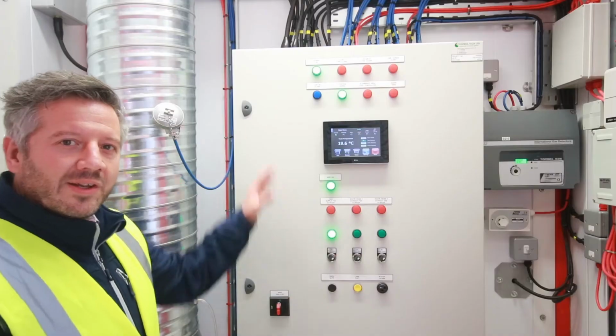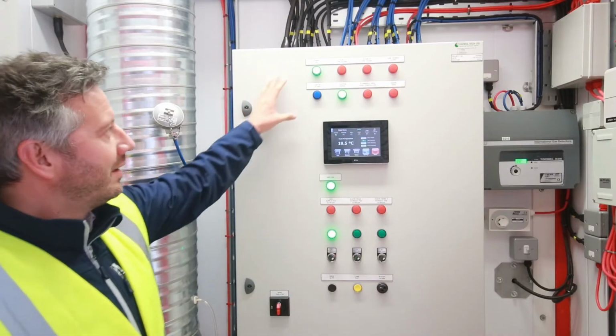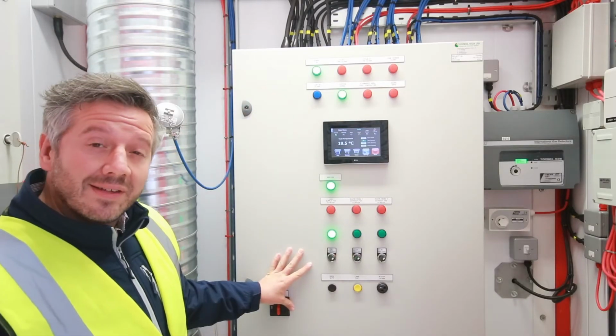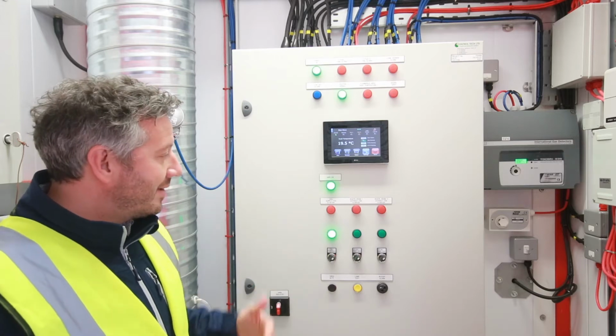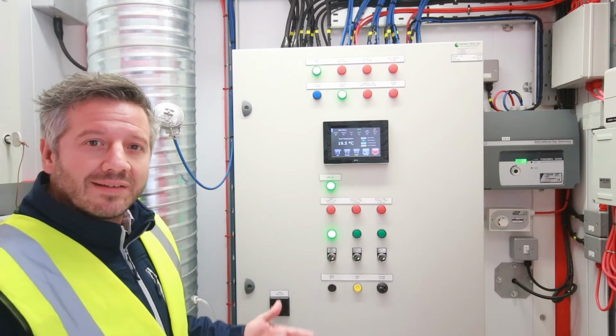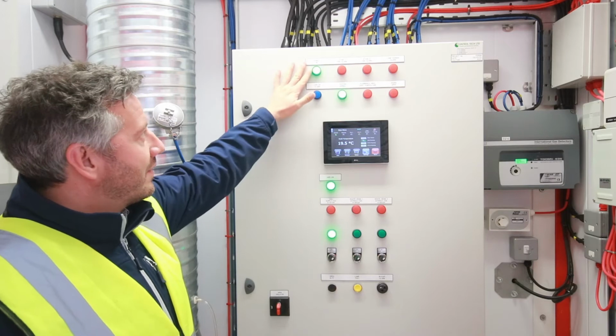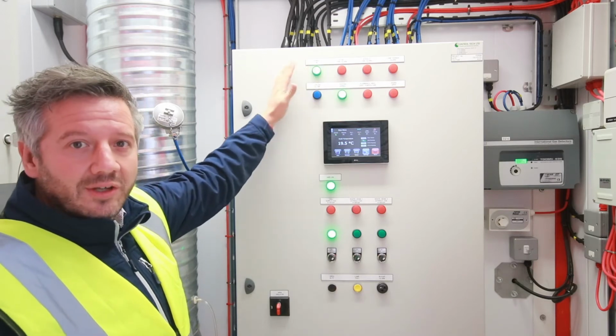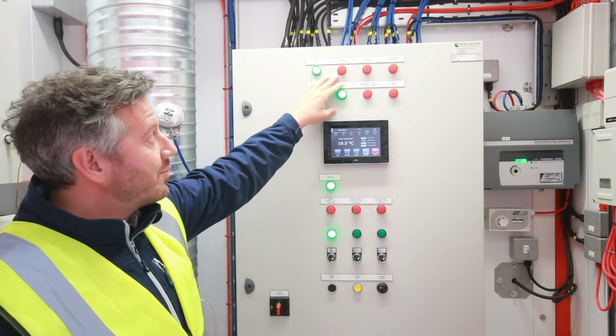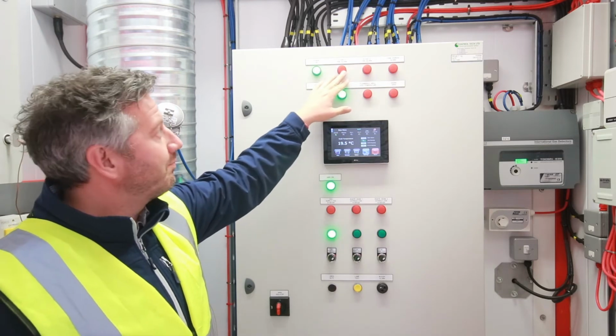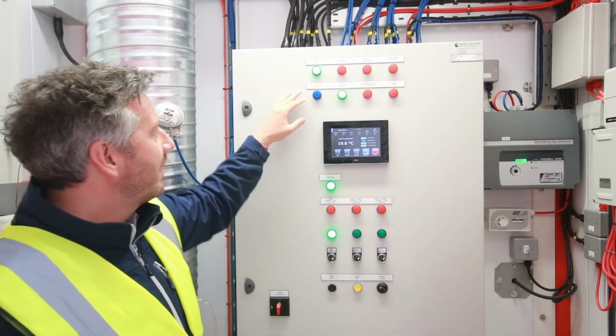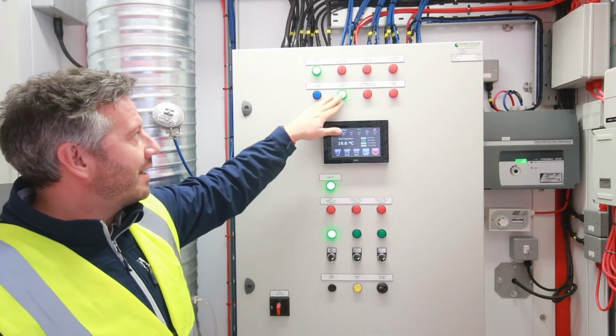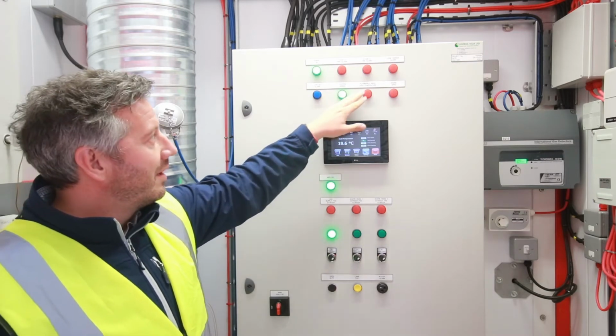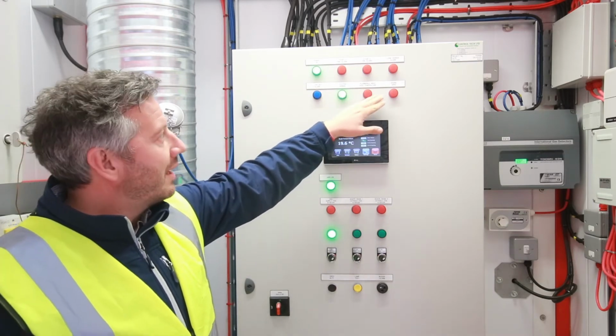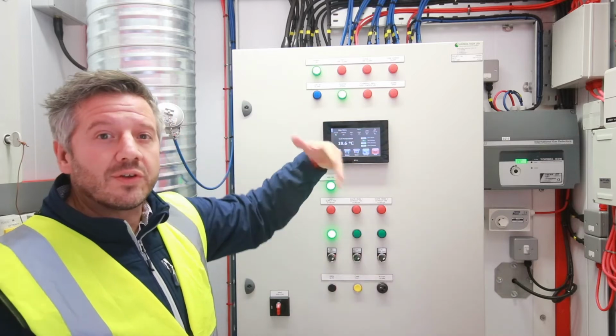for a Firevault. So here we have a typical panel. It's covered in indicator lights to give feedback as to the running of the system and any alarms that are active currently. At the top we'd always have a power on indicator, so you know the system is live. In this case we've got a two-stage fire alarm, a lone worker alarm, a low O2 alarm, again a system normal indicator, an over temperature alarm, and an indicator to let you know if the doors have been left open.